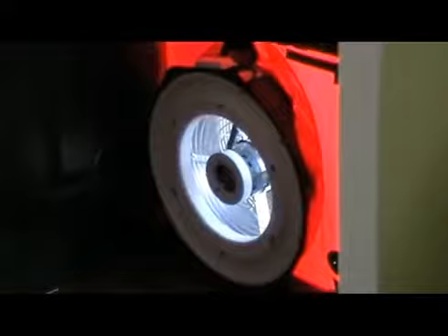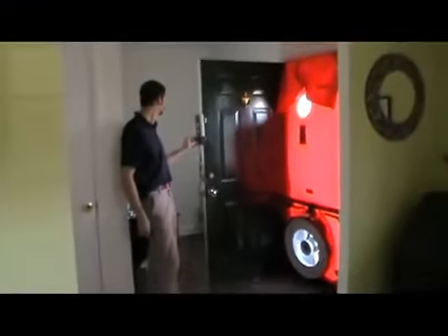But the main thing is it's going to tell us what the actual cubic feet per minute of air is leaking out of the home. Now when we compare what it actually is leaking to what the standard should be for a home of that size, we can determine if the house is really tight, maybe needing mechanical ventilation, or if it's very leaky, in which case we'd be looking at doing some air sealing, some insulation, things like that, to lower that number to get as close to that optimal number as we can.